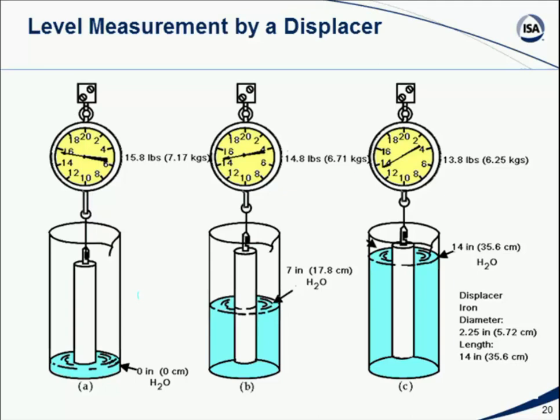And in the middle part of the diagram here, we can see that our water level has gone up halfway into the tank, and our displacer now seems to have a hanging weight of 14.8 pounds instead of 15.8 pounds. Its weight has reduced by 1 pound. Well, obviously its weight hasn't gone down. What's happened is that the pulling downward force of its weight is being counteracted by the pushing upward weight of the liquid that it has displaced, and therefore its apparent weight is 14.8 pounds.